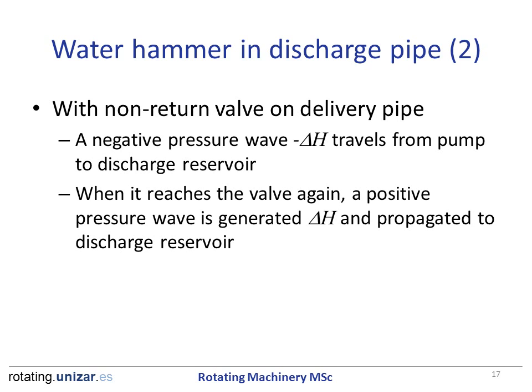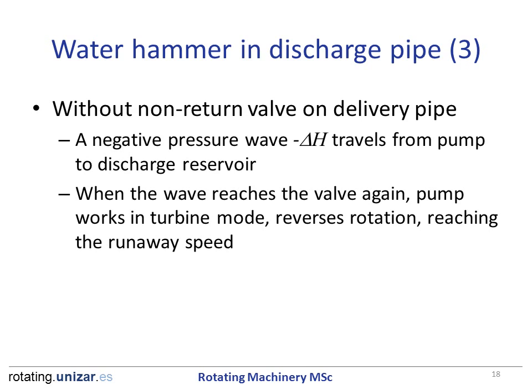The previous slides showed the behavior of water hammer with a non-return valve on the delivery pipe. If there is no non-return valve on the delivery pipe, when the wave reaches the valve again, the pump works in turbine mode, reversing rotation and reaching the runaway speed.